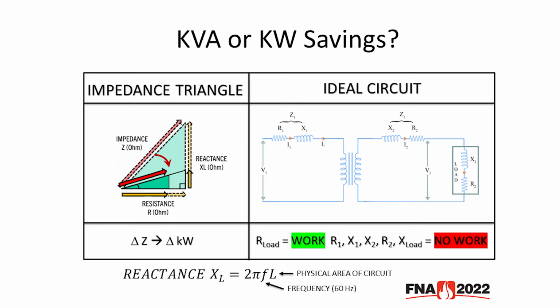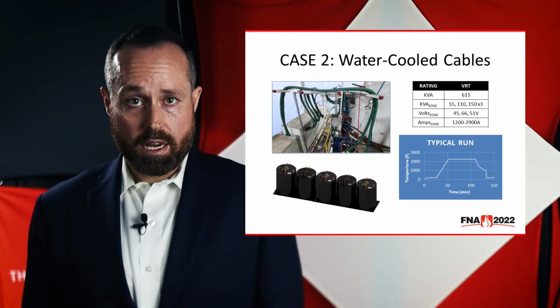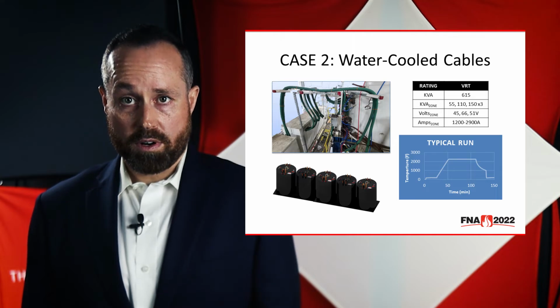It is also important to note that reactance is derived from the magnitude of changing current. Therefore, the high current secondary of a transformer has an exaggerated impact on the reactance losses within a system. This is another reason why we focus efforts on minimizing the size of a high current circuit within a system. This leads into the second example of an electrically underperforming furnace.